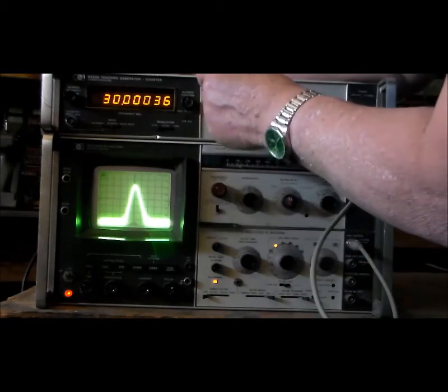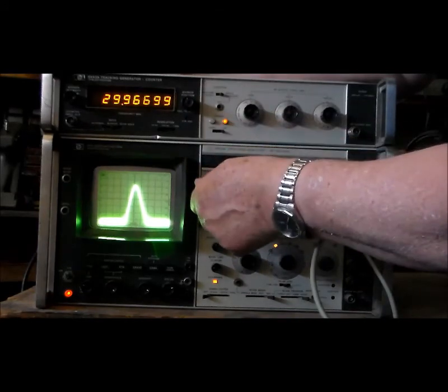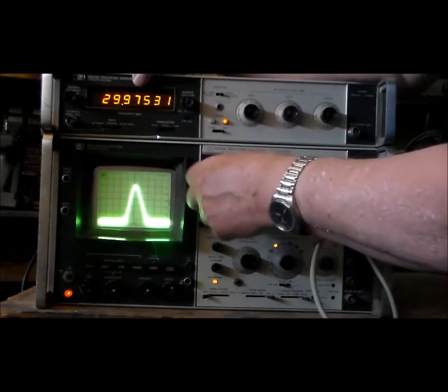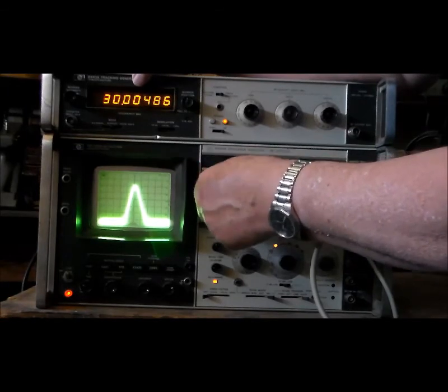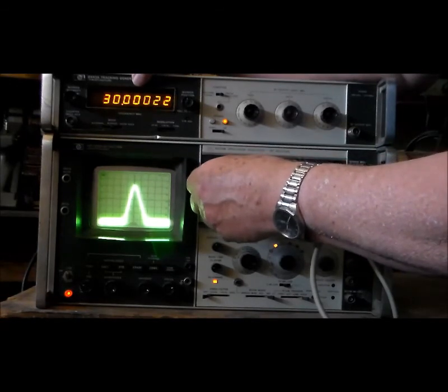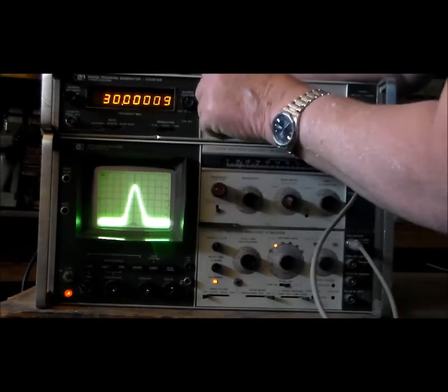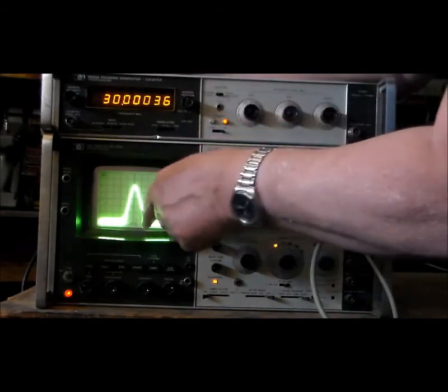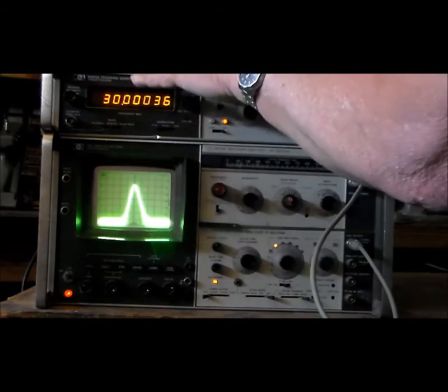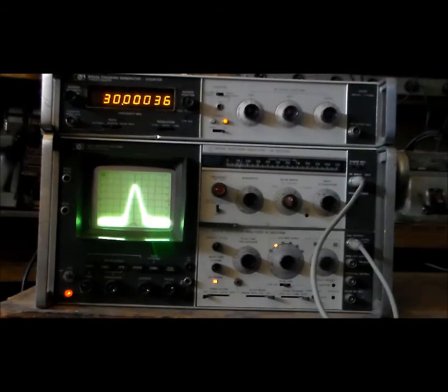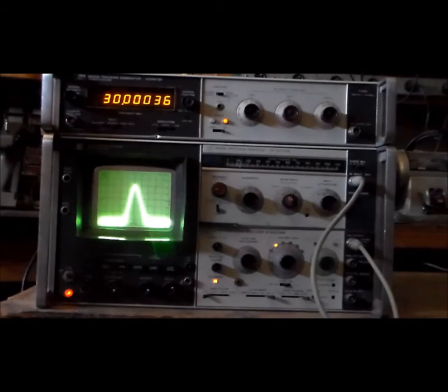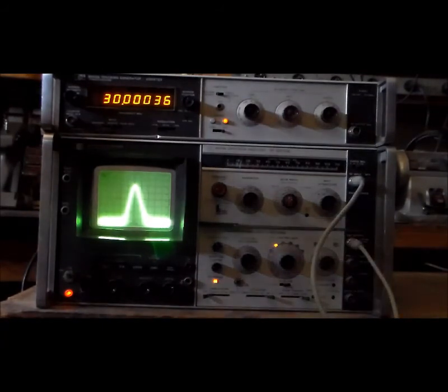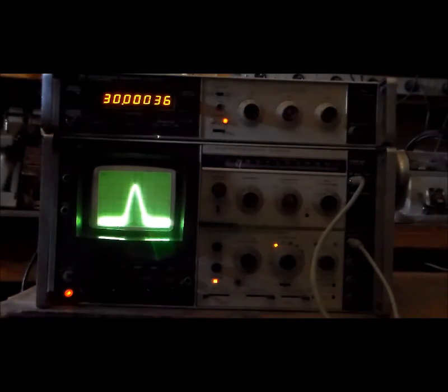But if I take it off of restore signal, you will see, here we are at 96, 96.6, 97, 98, 99. I'll dial in 30. Okay? But put it back to restore signal, we get the actual value of this within the accuracy of the time base of this guy. Okay, now, if there are problems with this system, the problems, 99 times out of 100, are the interconnect cable.